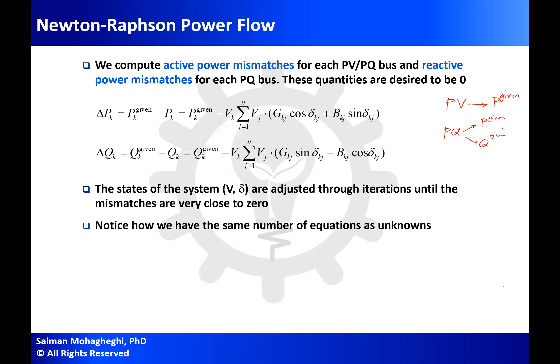Now I create power mismatch equations. Recall that when finding f(x) = b, I form a mismatch equation b - f(x), which is multiplied by the Jacobian matrix. Here, B would be the given values of P and Q, and f(x) would be the equations for active power and reactive power at node k. For active power, I have the given value minus the equation — referred to as F_P at node k to indicate it is a nonlinear function.